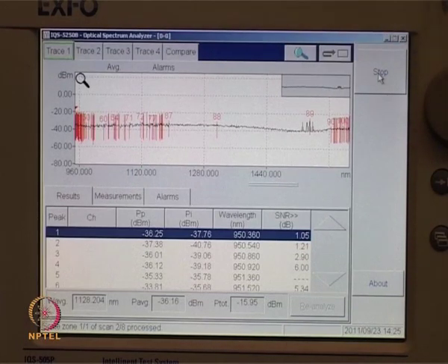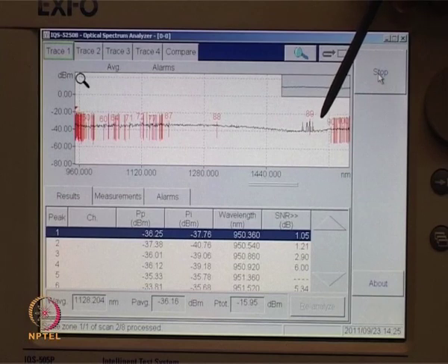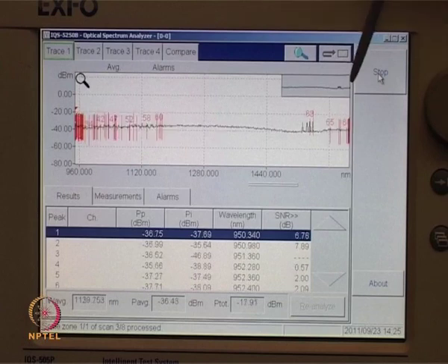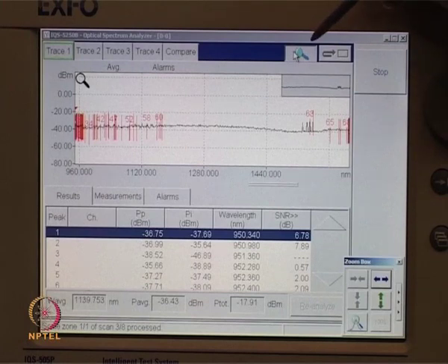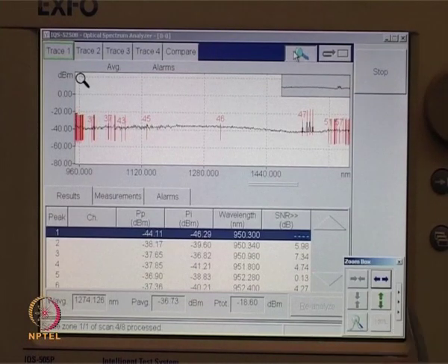Now you can see all the 4 peaks are of more or less the same values. Still the scanning is continued, as the calibration is not of a single reading but a display of an average of multiple readings.